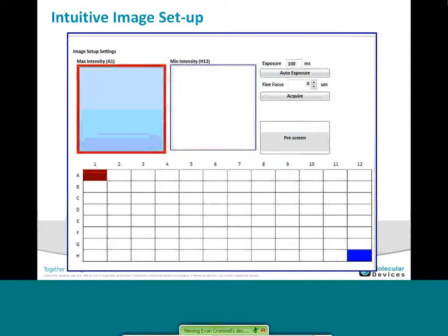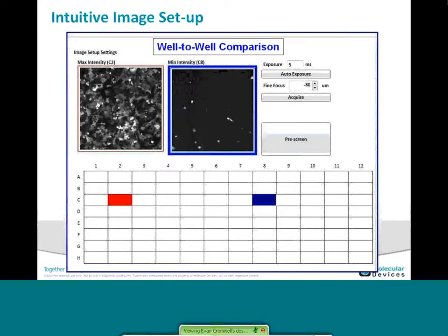Regarding intuitive image setup, we allow you to look at either a maximum or a positive/negative control. You can then do a well-by-well comparison for your setup of the exposure. Fine focus will allow you to adjust for different plate types — we have several supported plate types, but you can also customize your individual plate in the system. Then you can zoom in, see the quality of your cells, and do a visual inspection QC before you start your assay.